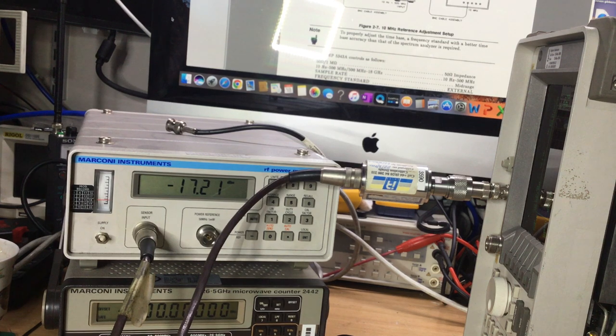So for example, the amplification of the frequency would be okay, in other words, but to adjust the level. However, we might not have the frequency accuracy because the varactor tuning diodes in the temperature control crystal oscillator might have failed, or it could be that there's a digital logic fault where the microprocessor is changing the DAC values through an op amp, a digital analog converter, and then varying a tuning voltage to the TCXO module. I could understand that not working, but then I would expect to see the amplitude there, which we haven't got. But for both faults to be present, that seems a little strange.